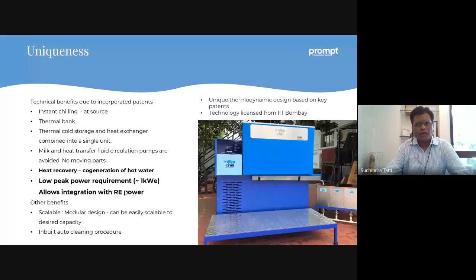There are no moving parts, no pumps. Even the flow of milk is through gravity. All of this results in very low energy consumption. The peak power requirement for this product is about a kilowatt. This has serious implications, because it not only results in huge energy savings, but also allows us to integrate with other sources of renewable energy. So the combination of heat recovery and the patented thermodynamic design results in one of the most energy efficient machines in this capacity and category of chilling.